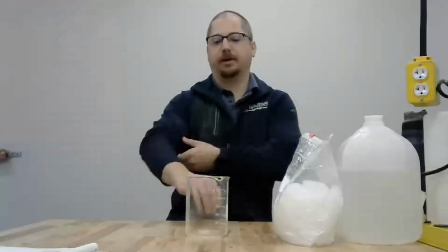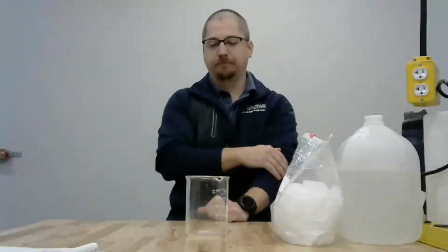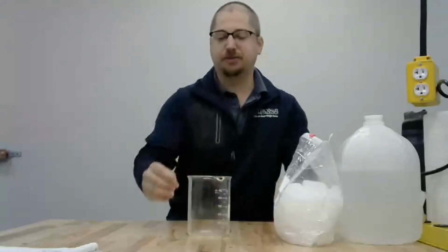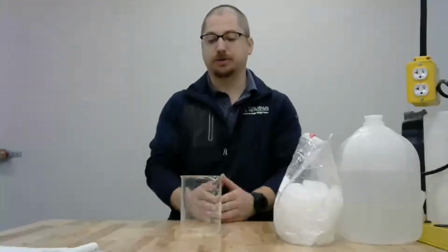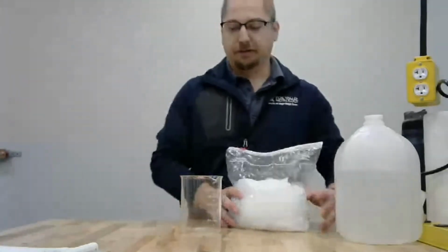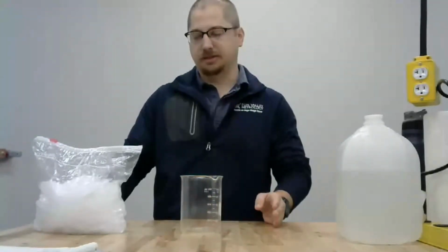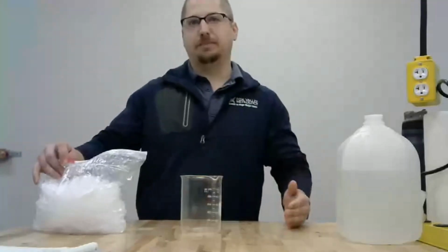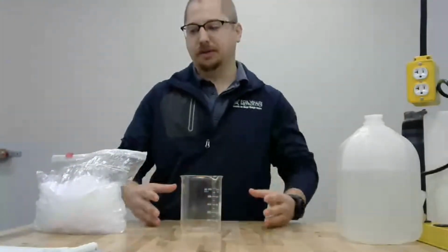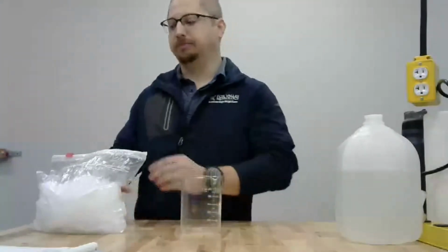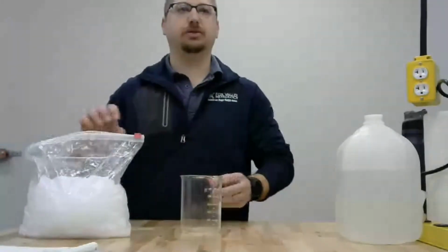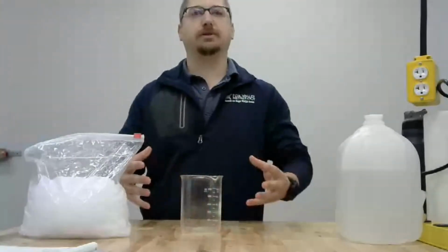Like Steve said, the ice point is a constant that you can use in your lab to verify your probes. It has a few simple steps to be done correctly in order to follow NIST guidelines. And if you follow those, that is what will drive that uncertainty down to 0.01 degrees Celsius. If you don't follow these steps, there can be a little bit of additional variability in the ice point. And that's pretty much going to be due to the packing of the ice compared to water.